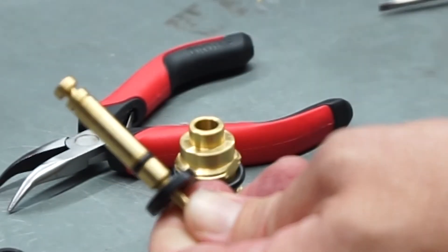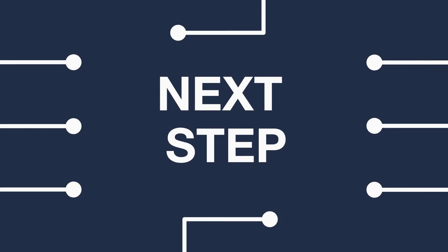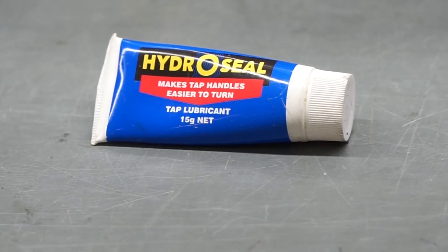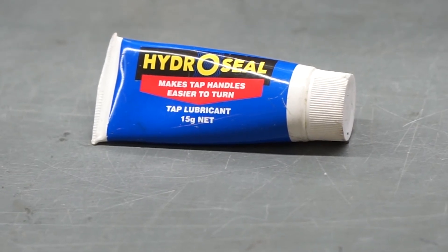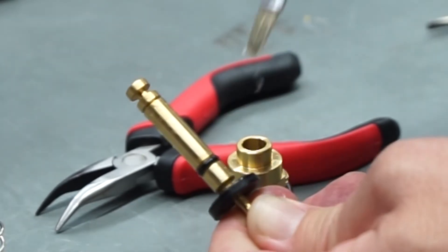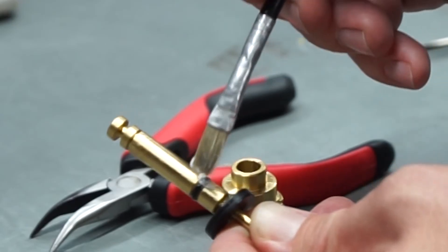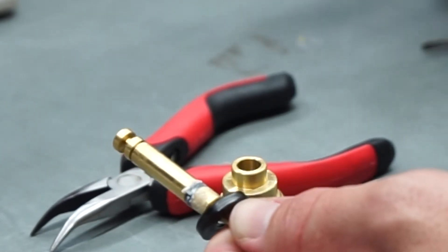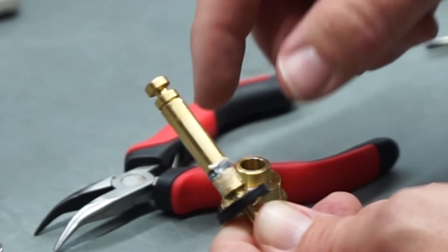This is the spot that you need to grease. I recommend using some HydroSeal grease — it's food grade and can be sourced from many of the plumbing merchants. With a little art brush, just grease that spindle where the O-ring is. This is where it's going to catch when it's been running for a while and the grease is removed.